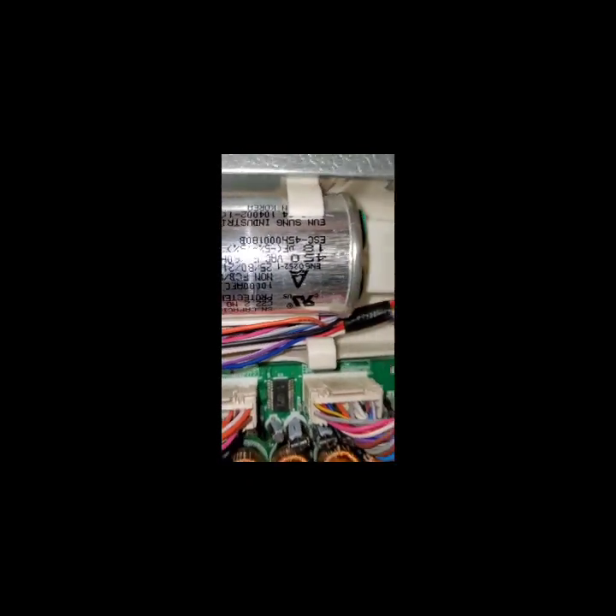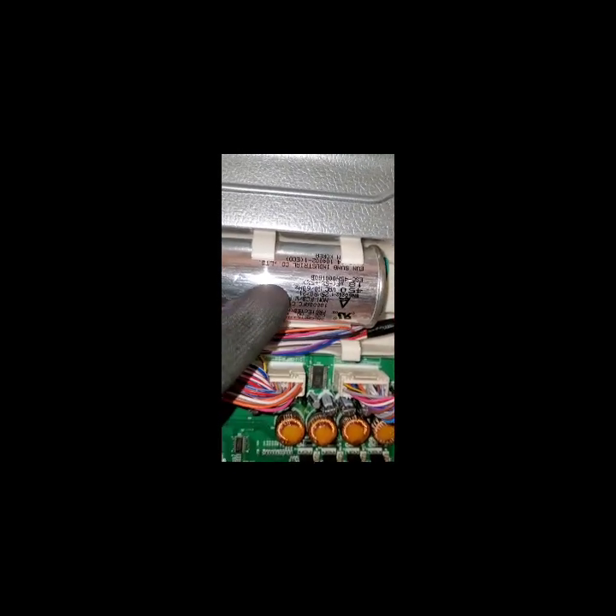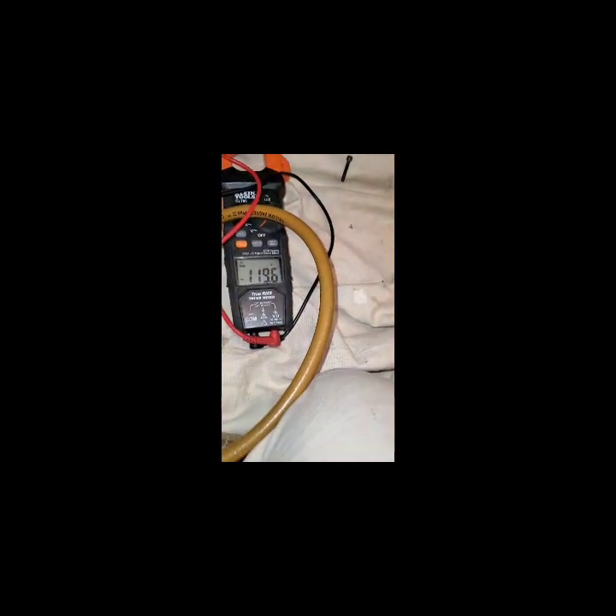Now, this is 30 seconds here. Another thing I wanted to point out: that's your capacitor. I went ahead and also checked that. It tells you the specifications of the farads. I think mine was 18 microfarads. I did check that and it did check good. So it's been about 30 seconds now and this volt meter has not indicated that the board sent the 200 volts, and that right there is how I know I have a bad board.